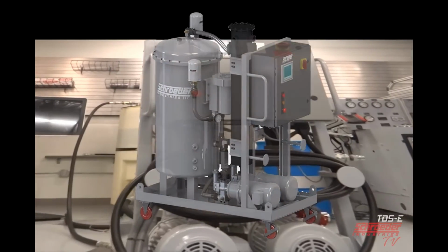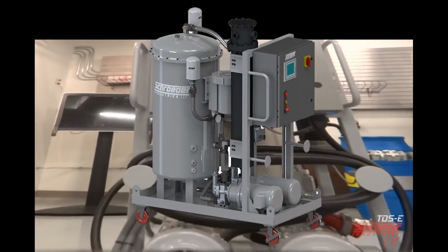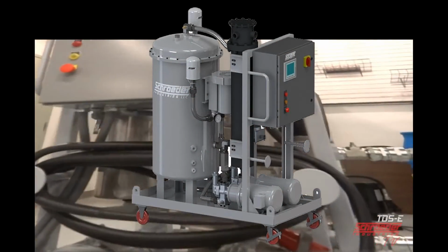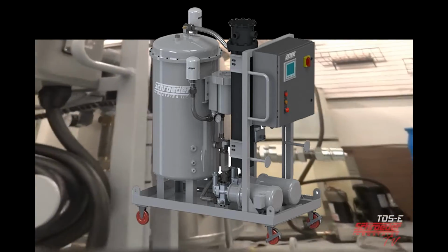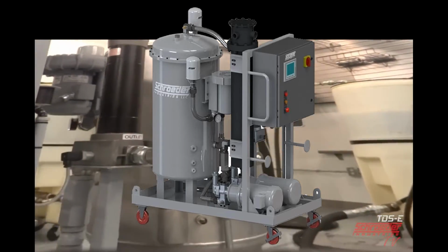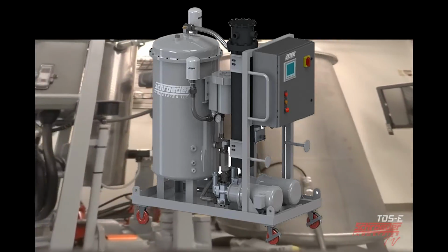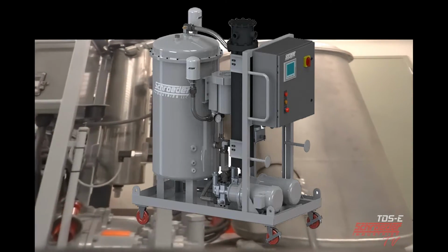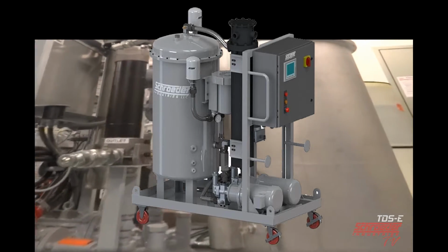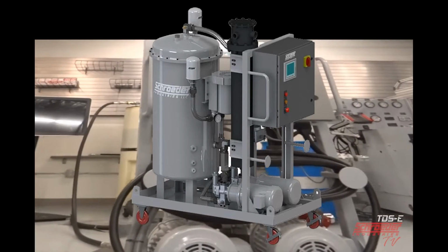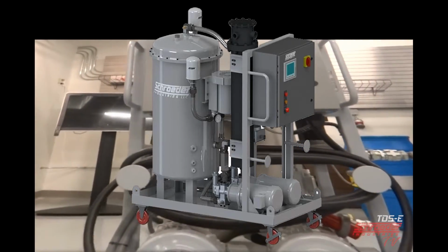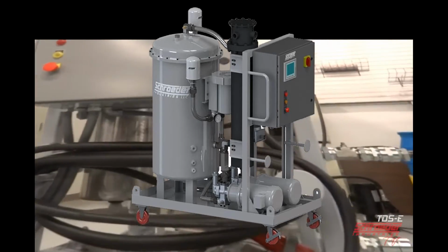The Triton unit is equipped with a remote start option. To start auto mode remotely, connect a 120 VAC maintained signal. To stop auto mode remotely, a remote start signal must first be present and then removed. All local controls can override the remote start signal. You can also enter manual mode and exit auto mode and shut down the motors.